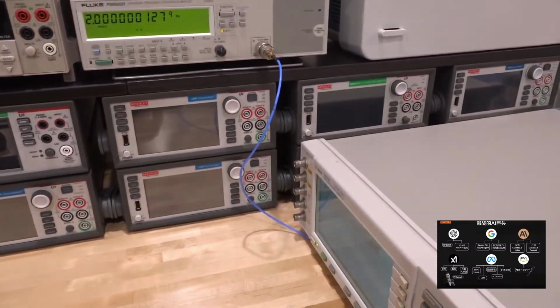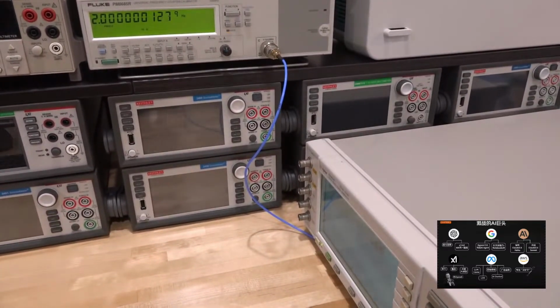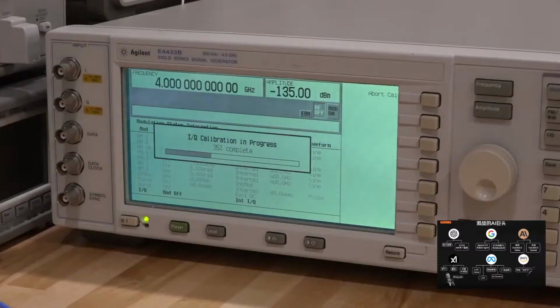So now really the only thing we haven't tested is some of the modulation functions. Of course, there's a lot more to do. But for us, if we get the modulation working, then we're fairly satisfied that the instrument is good. Before we do any IQ measurement and any modulation measurement, let's do an IQ calibration. And if this thing succeeds, this itself tells us that the internal measurement capability and calibration routines are actually working. So that's a good one. Let's wait for this to finish.